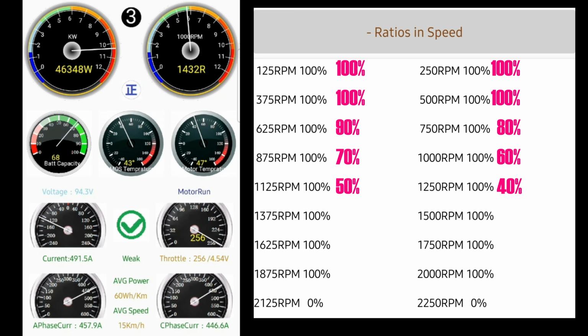And look what happened to the volts. It came up above the 13 volt sag, 94.3. So we're actually good, but we're not good for long. It's going to sag pretty strong starting after this. If I bring it up to 1625, it dumps down to 93.2. So right in there, we're talking about a 15 volt sag. So we want to correct that. And that's one of our options on ratio and speeds. We want to have a limit in there.